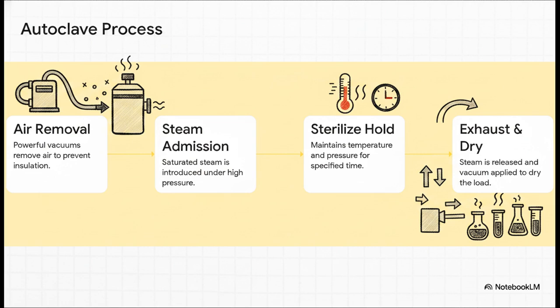Air actually acts as an insulator, so it's the mortal enemy of sterilization. They use these powerful vacuums to suck it all out. Step 2 introduces saturated steam under intense pressure. Step 3 is the sterilization hold, which usually means baking the load at 121 degrees Celsius for a good 15 to 30 minutes. And finally, Step 4 exhausts all that steam and pulls yet another vacuum to dry the load completely.